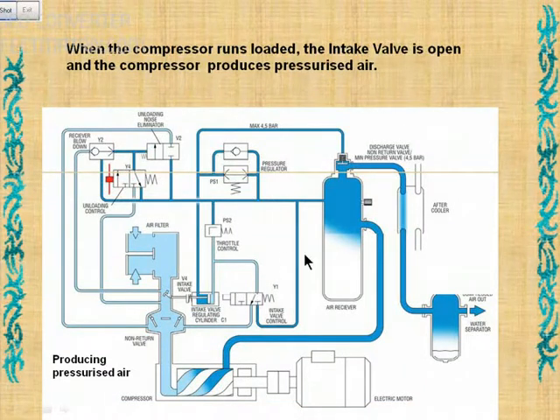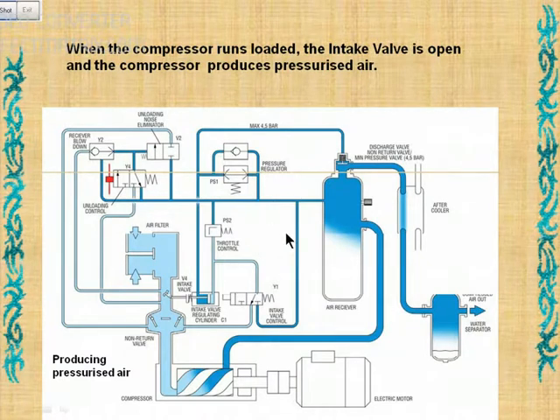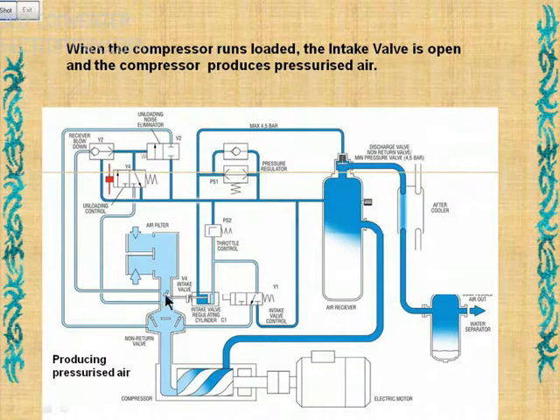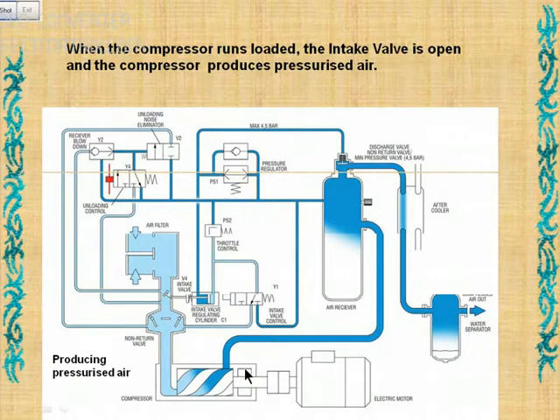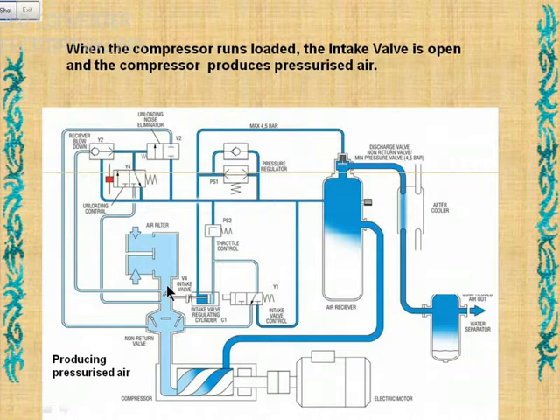This is the schematic diagram of the compressor when running at full load. When the compressor starts, this suction valve is kept closed against the spring. There is a spring here and this will be kept closed, so that the current drawn is less during initial start. So initially the motor starts with star, then changes over to delta after a few seconds. So no air is taken in — there is no load at this point.